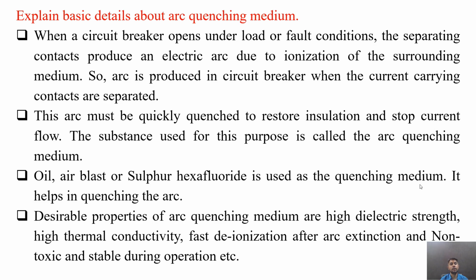Explain basic details about arc quenching medium. So when a circuit breaker opens under the load or fault conditions, the separating contacts produce an electric arc, because whenever the moving contacts are separating from the fixed contacts, it produces the arc due to the ionization of the surrounding medium. So arc is produced in the circuit breaker when the current carrying contacts are separated. So this arc must be quickly quenched to restore the insulation and stop current flow. The substance used for this purpose is called the arc quenching medium. Oil, air blast, sulfur hexafluoride, vacuum, etc. is used as the quenching medium.